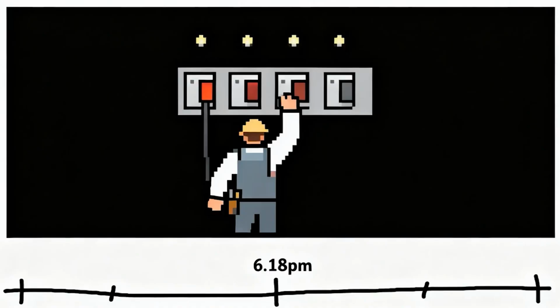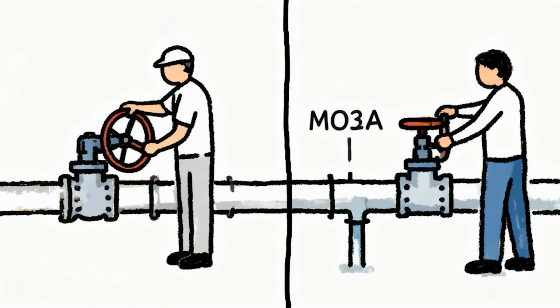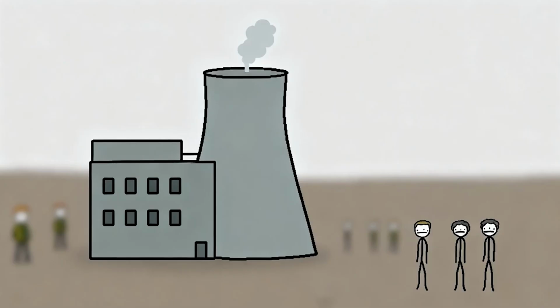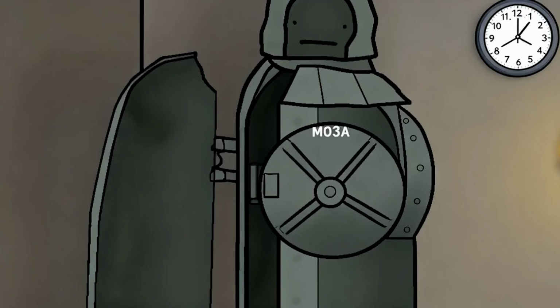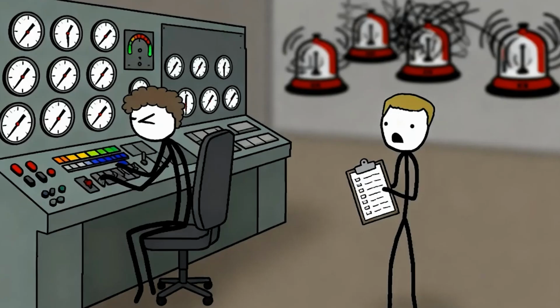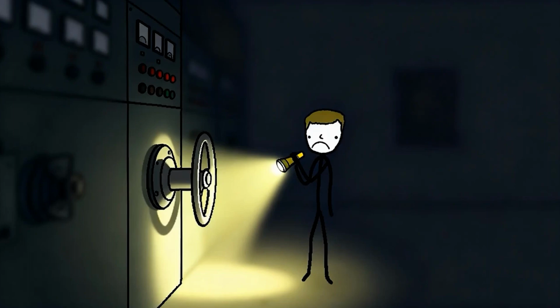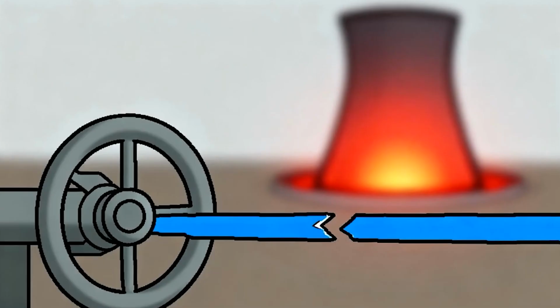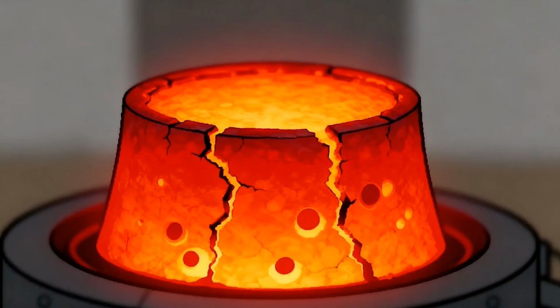By 6:18 p.m., some DC power was partially restored. Operators tried to reactivate the isolation condenser by opening valves MO3A and MO2A. They saw steam briefly, a hopeful sign that cooling had resumed, but 7 minutes later at 6:25 p.m., MO3A was found closed again. The reason remains unclear. Some reports suggest operators misread indicators in the chaos, others point to procedural caution, operators worried that opening the valve during a blackout might cause uncontrolled leaks. Either way, the valve stayed shut, cooling stopped, and the reactor core began its slow march toward meltdown.